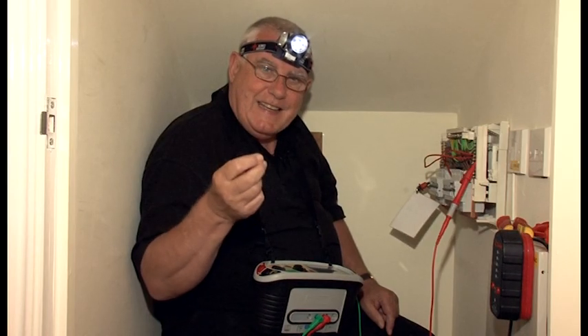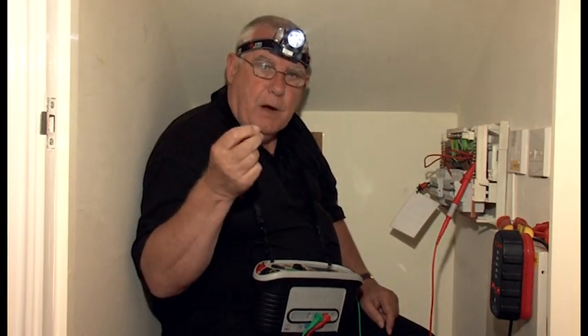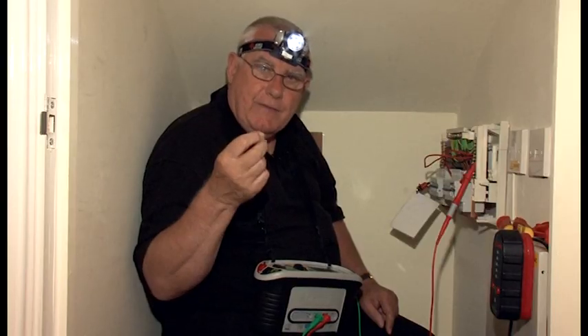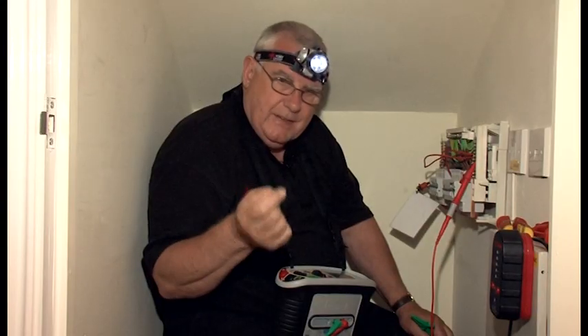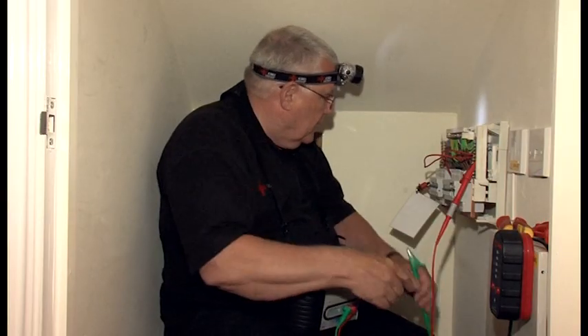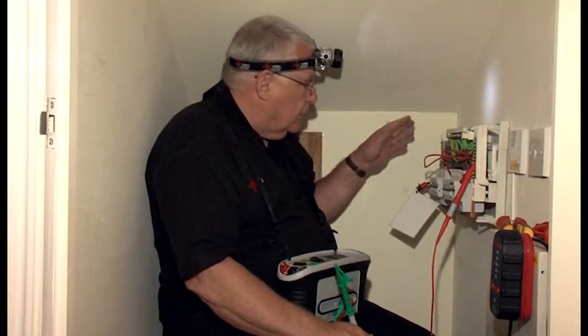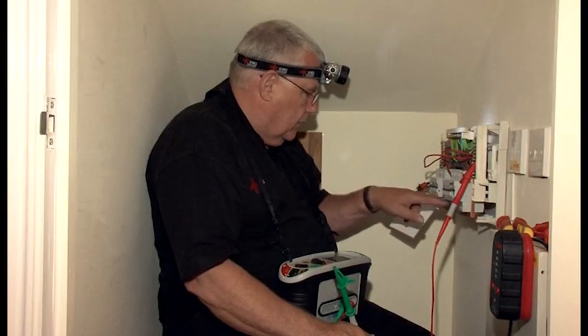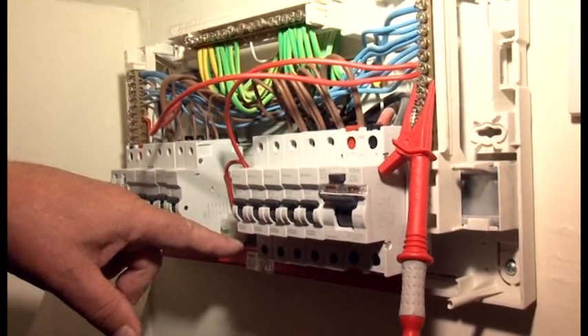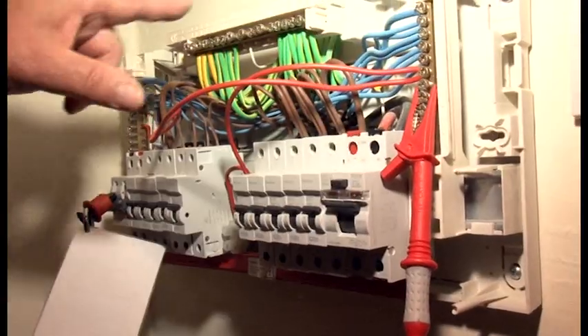So that's why I'm undertaking this test after we have verified by both inspection and test that we have an earth. Testing with line and neutral cross-connected means that equipment such as lamps will not interfere with the resistance readings. And electronic devices will also not be damaged, so they can be left in the circuit. Light switches must be in the on position, as are all circuit breakers and RCDs. Now this is actually proving to be a bit of a bugger here because it's a split load board. So to join line and neutral together, I'll join the two lines together there, the two neutrals together there, and the line to neutral there.